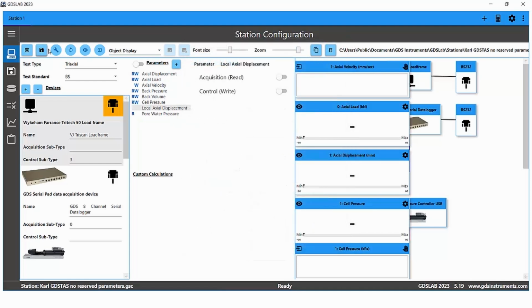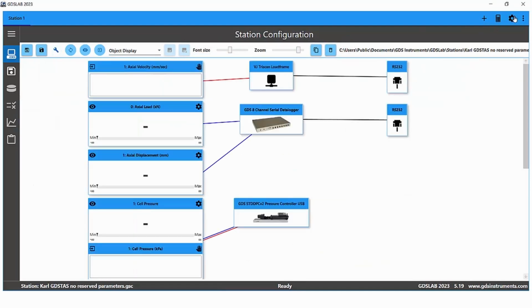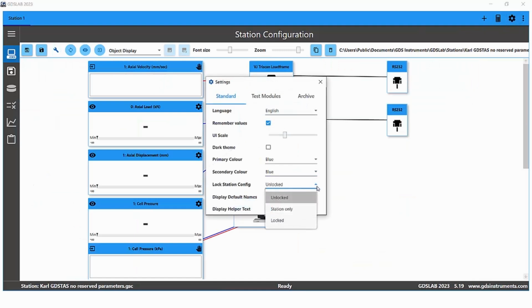transducers. Now, if I go to the settings, you'll see I have two options. One where I can lock the station only, which prevents the user from changing the station configuration, but still allows the user to change the transducer parameters, or locked, which locks both, so the user cannot change the station configuration and cannot change either the transducer parameters.